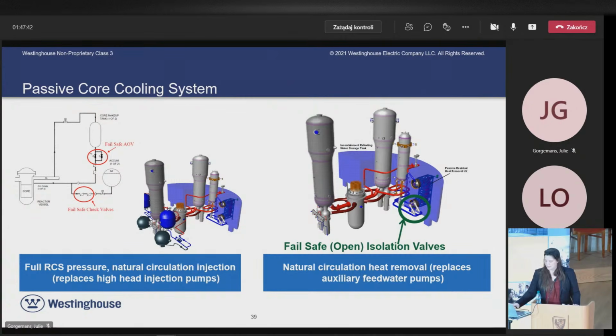The outlet line, which comes from the bottom of the tank and goes to a dedicated line for injection into the reactor pressure vessel, is not firmly insulated. So any heat contained in there will be dissipated into the containment building. Because of that, it's much colder than the inlet line. The core makeup tanks are isolated by one valve, normally closed when we are operating. In case of an emergency, if we have an excursion in parameters that trips the reactor automatically, the plant protection system will also activate those valves to open. We only need one of them to open.